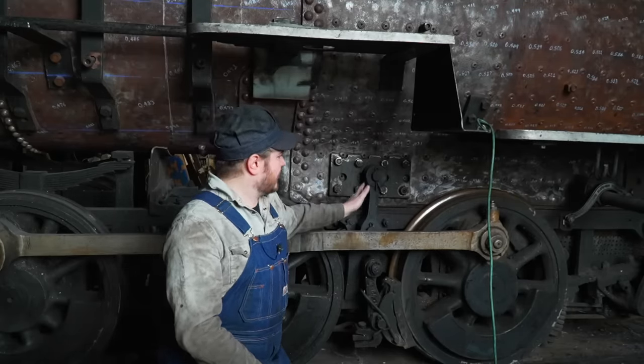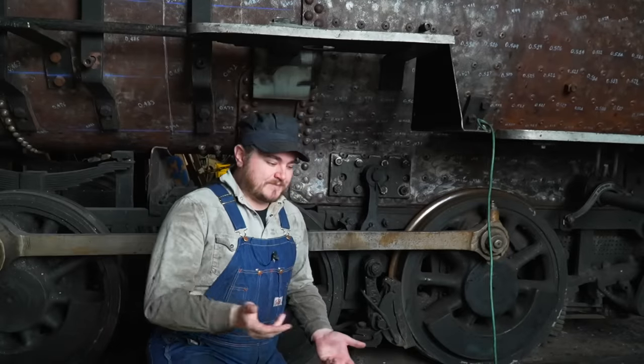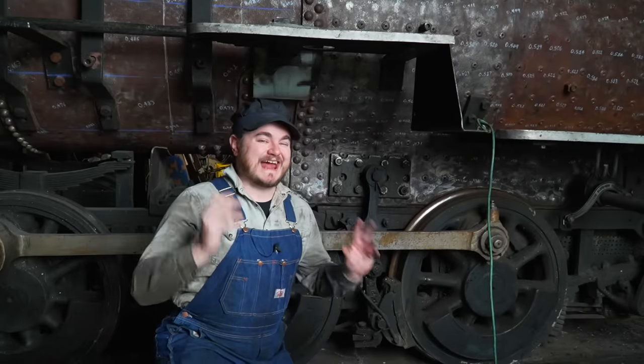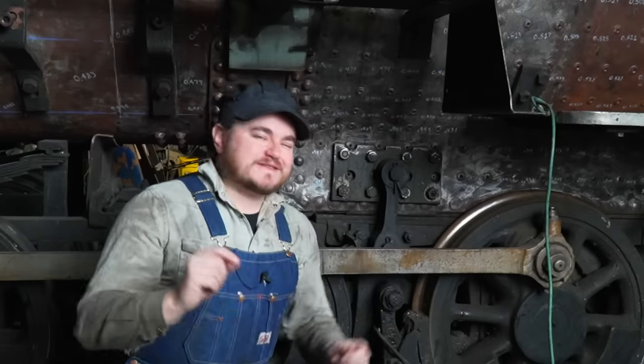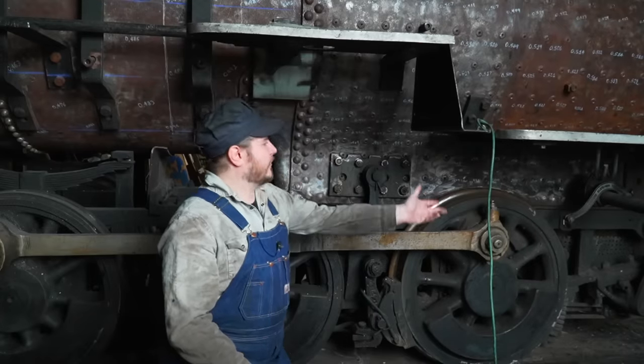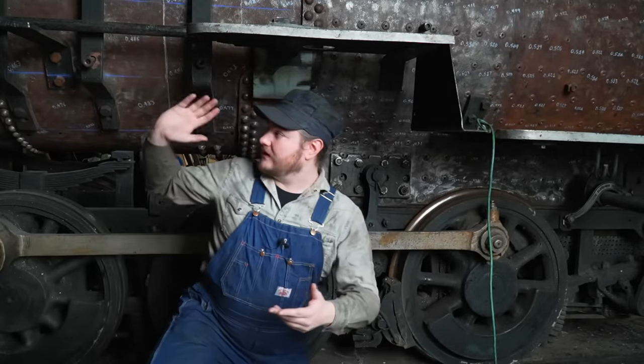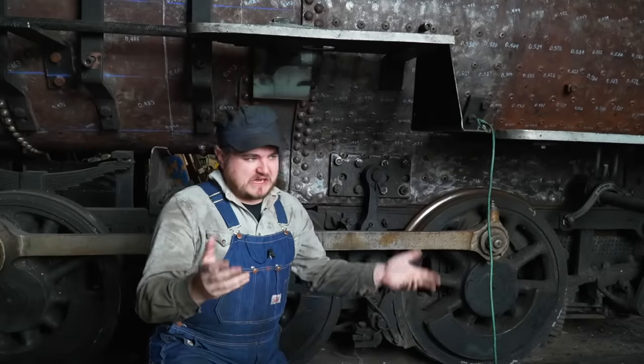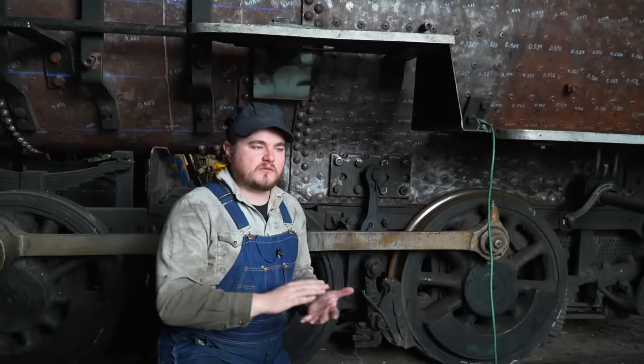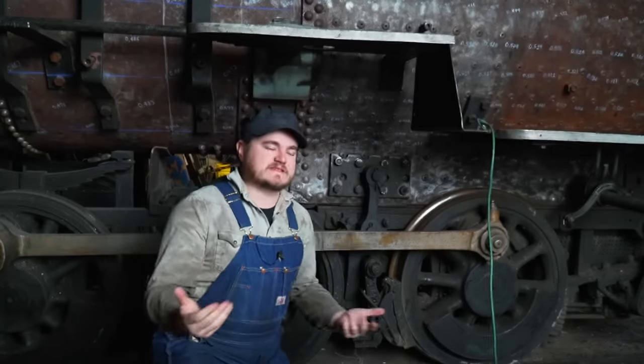And so all across this boiler, mostly originally half inch sheets, well, now it's a little bit less than that. You know, maybe it's 10 thousandths less, maybe it's 100 thousandths less. And so the FRA allows you a minimum thickness. You need 60% of what you originally had there for much of the boiler, but you also still have to meet that minimum safety requirement of a safety factor of 4. And so we survey the boiler at a bunch of different places, specifically on a grid to get a good amount of data points across the whole boiler. And we figure out, okay, well, we've got a nominal average kind of what the sheets look like, and we find the worst spots we can, and okay, we'll use those for the calculations. That'll be the safest thing.